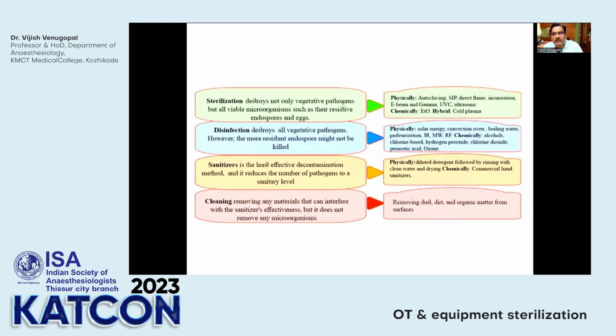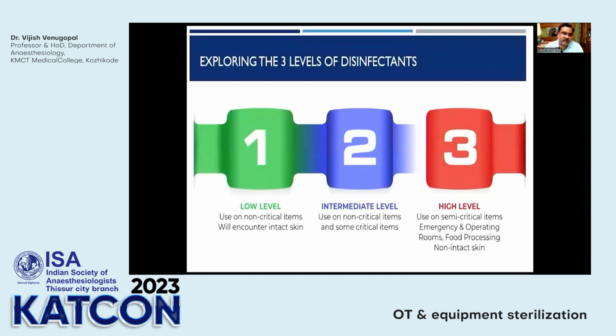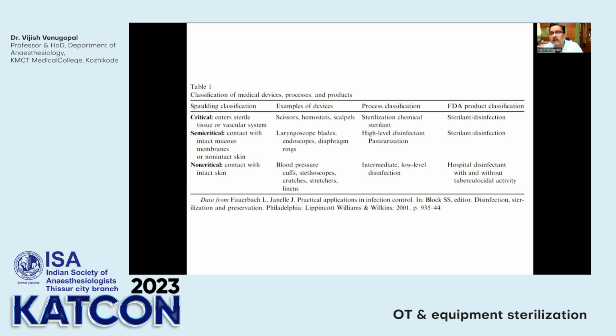But it does not kill the prions. For prions, we require the prion reprocessing. Now, there are certain levels of disinfectants: low level, intermediate level, and high level. The low level ones are the alcohols, the intermediate ones are the iodophores, and the high level ones are the aldehydes, that is the glutaraldehyde, Cidex, and all that you use. So there are different levels of disinfectants, and where they should be used depends on the medical device that is being used.